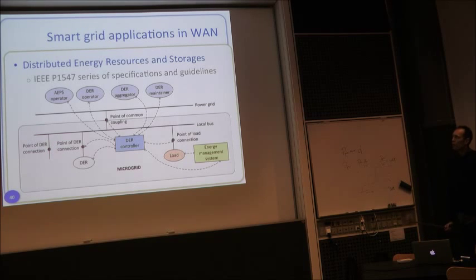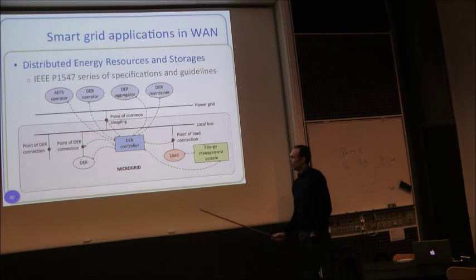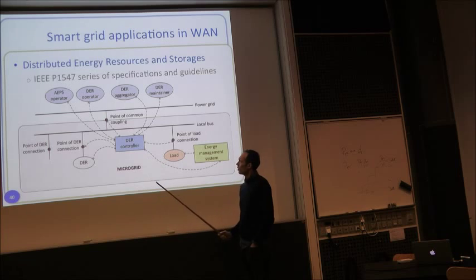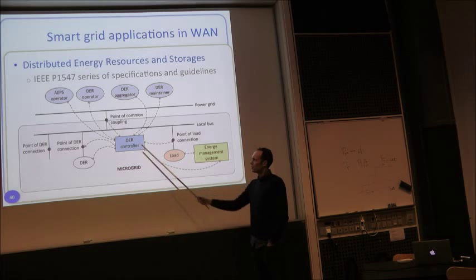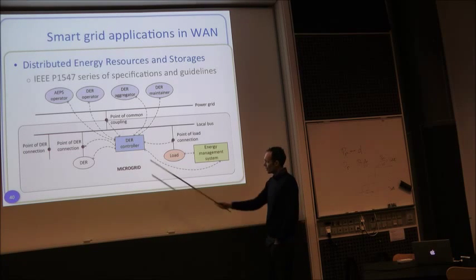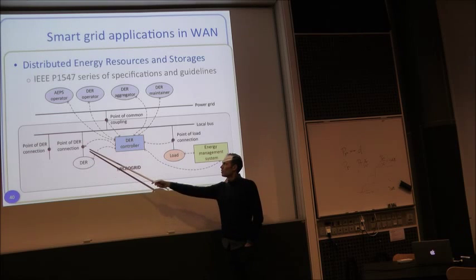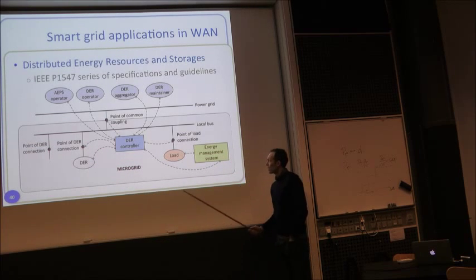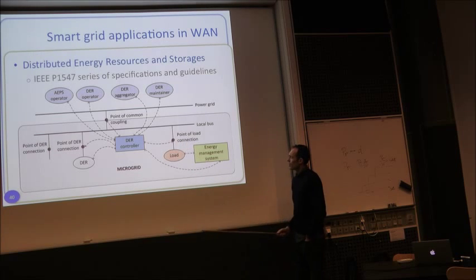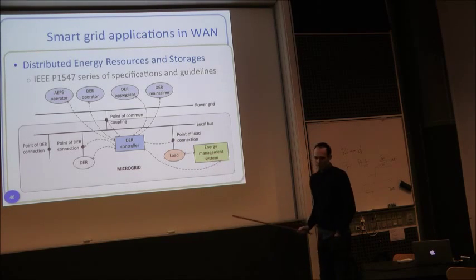This is the logical topology of the microgrid communication network. So there are some logical entities. The controller resides within the microgrid, but in grid-connected mode it actually receives control information from the outside, and if islanding occurs, then this controller takes over. This controller should gather data from energy sources, also their points of connection, loads, and their points of connection, and maybe from some energy management system which controls the behavior of the loads.